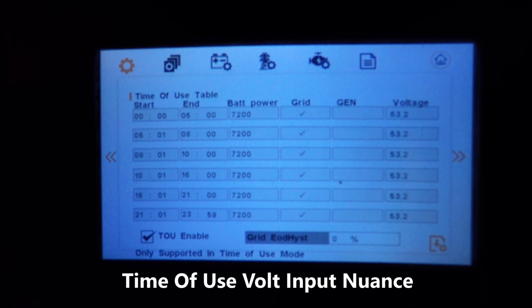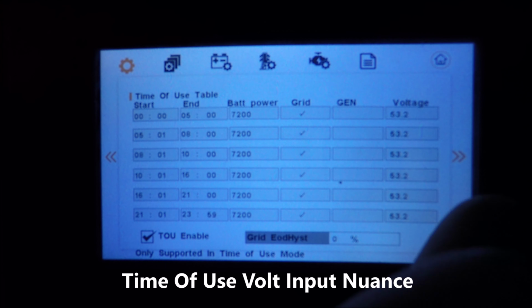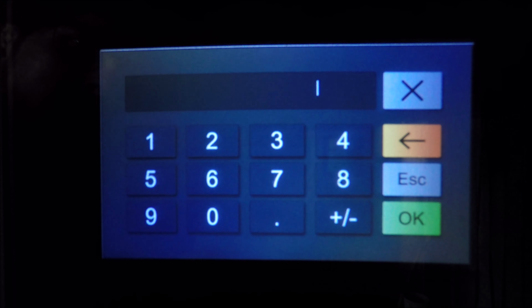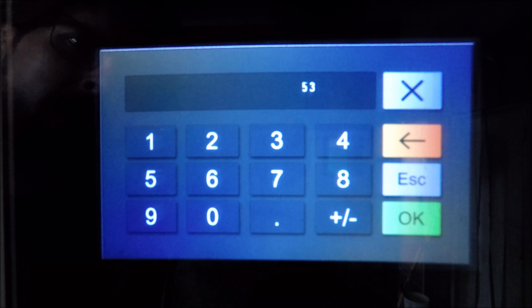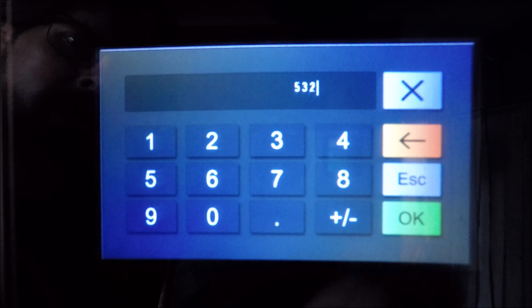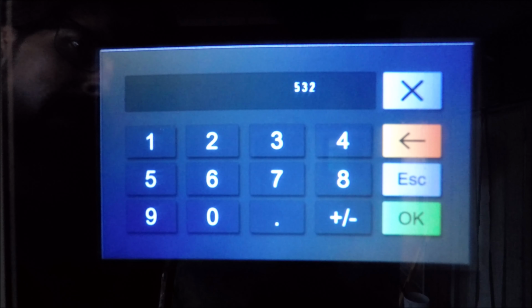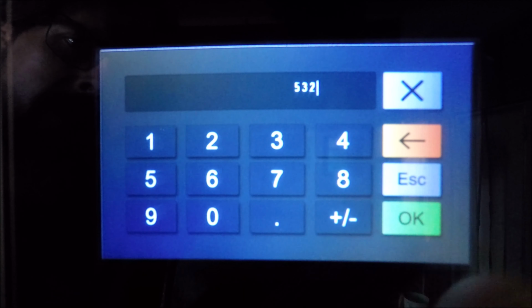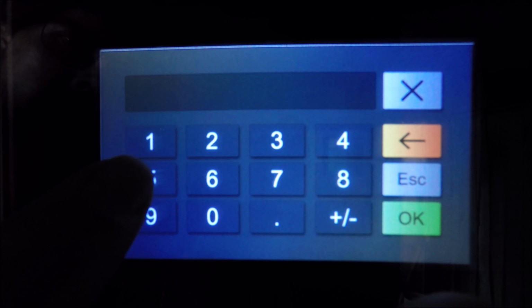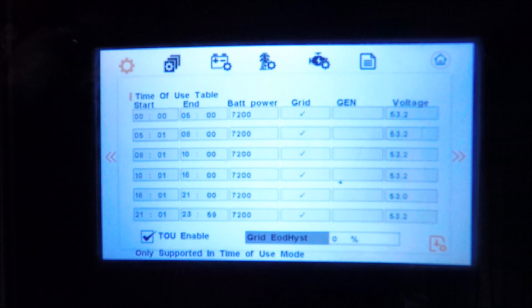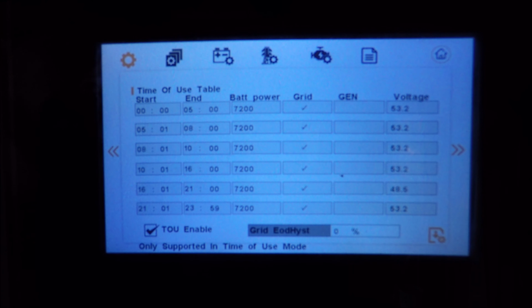Now I want to show you something here. This is very important in time of use when you do these setups. If I just put 53 and hit OK, it won't do it. It needs 3 digits entered here, so we want 53.2. It also doesn't like the decimal point. So you always have to make sure that you enter 3 digits. If we wanted 53 volts there, it would have to be 530. Notice, because we are using a custom battery type, instead of percentage here, it's in voltage.